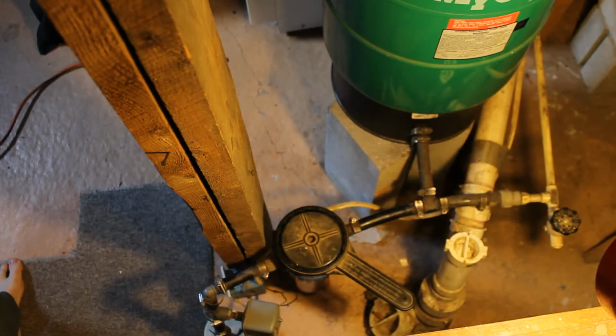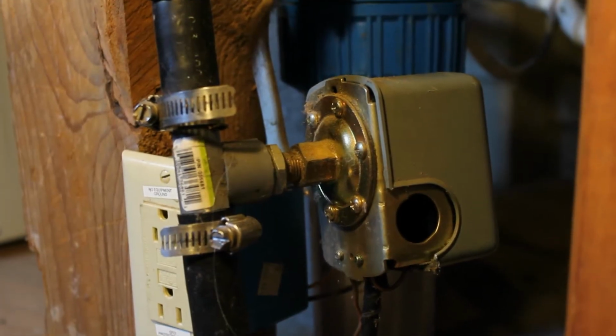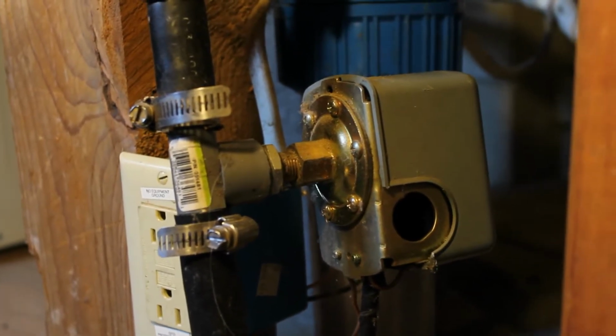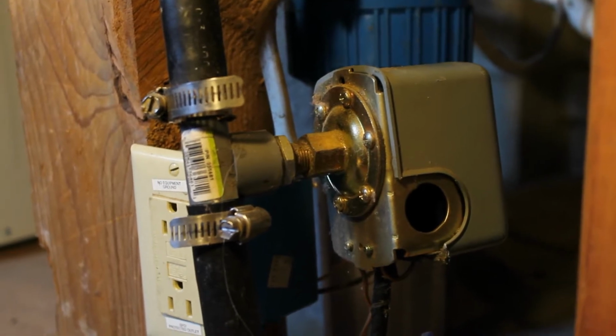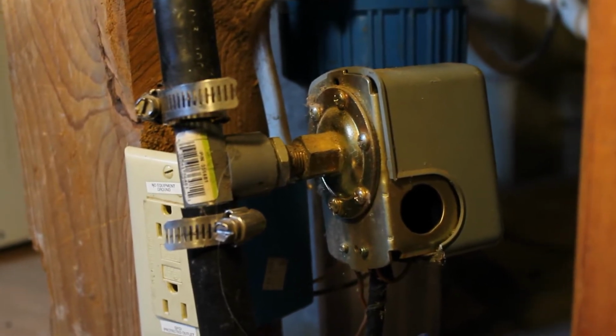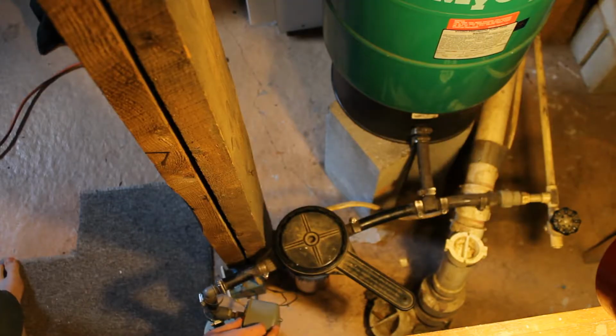This is where the water pipe comes into our house, and this is a pressure sensor. We have it because one of the failure points for the pump is that the internal pressure sensor fails, meaning the pump just keeps pumping. We've eliminated that by installing this pressure sensor, which cuts off electricity flow to the pump once the pressure reaches what we want. The pump is the most failure-prone part of this system, failing in a way we can't get around, approximately on average every 3 years. It's rather random and doesn't fail continuously, so we always keep a spare one on hand.